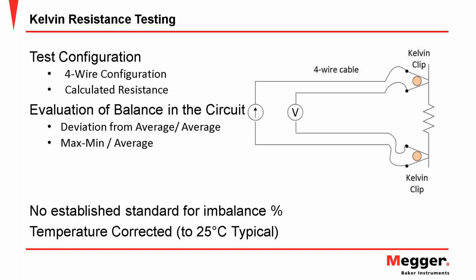But again, as I mentioned earlier, there are exceptions, such as concentrically wound random motors. Those types of windings have some inherent imbalance due to the nature of how the coils are laid into the slots. And of course, if we're comparing values to standards, so if we're an OEM, for example, a manufacturer, and we know exactly what the winding resistance should be, we could use that as a standard as well. But we have to remember that for that reading to be meaningful, we have to temperature correct that value. It's very common that those values are corrected to 25 degrees C, but there are, again, variations in that temperature correction standard as well. Some manufacturers might correct to say 20 degrees C. I've seen that one from a Japanese fork truck manufacturer before.